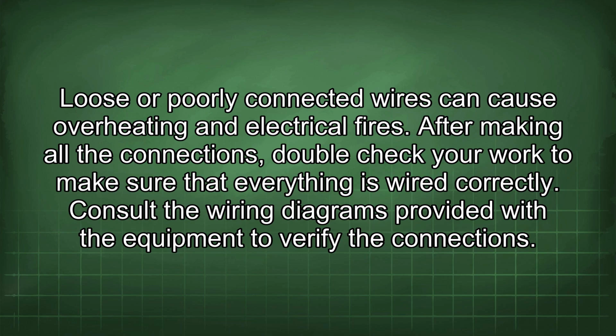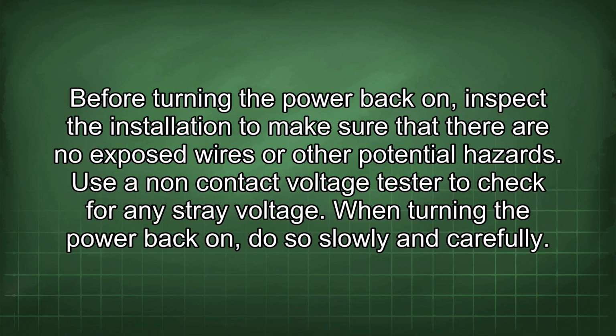After making all the connections, double-check your work to make sure that everything is wired correctly. Consult the wiring diagrams provided with the equipment to verify the connections. Before turning the power back on, inspect the installation to make sure that there are no exposed wires or other potential hazards. Use a non-contact voltage tester to check for any stray voltage.